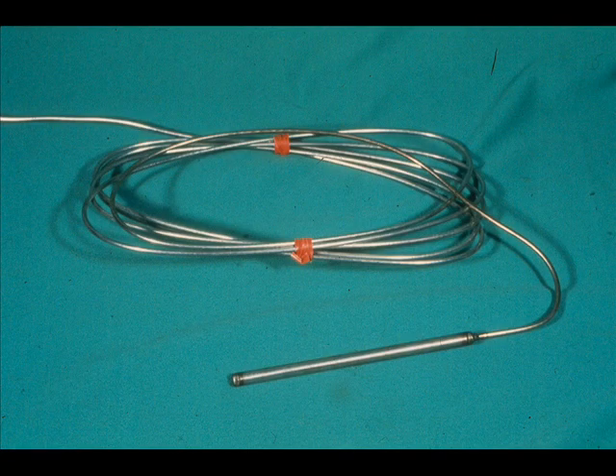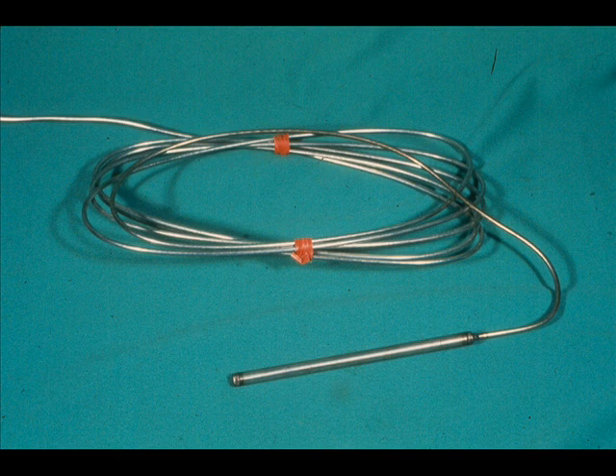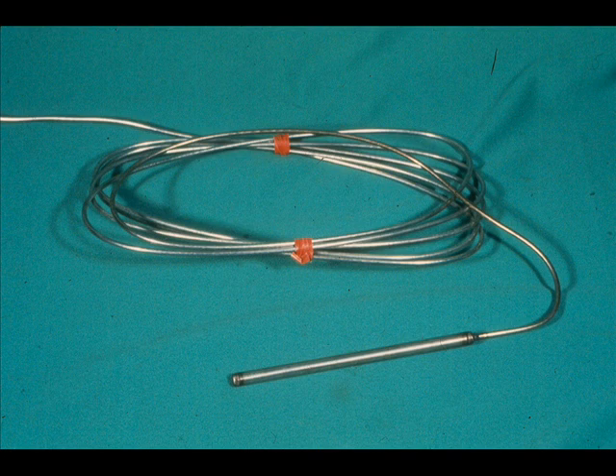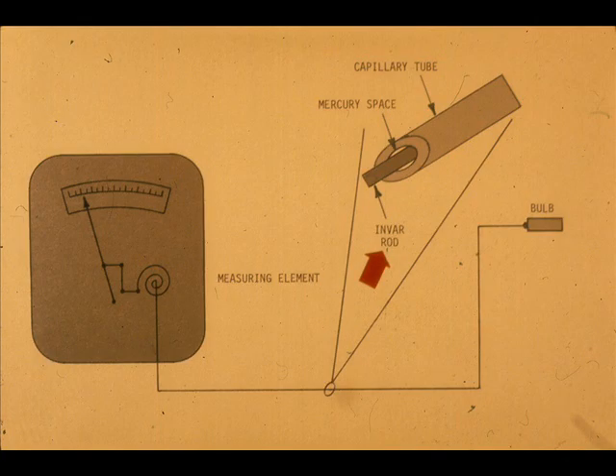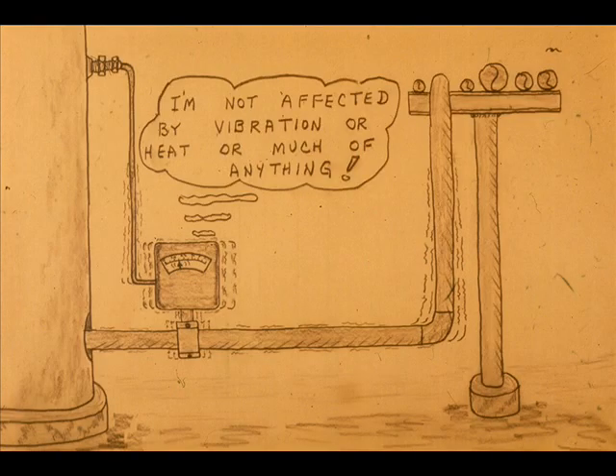The high filling pressure gives the mercury system a positive positioning action and good response speed. This high internal pressure also makes the system immune to changes in static head pressure caused by moving the bulb above or below the case. The case and capillary temperature compensation is accomplished the same way as in the liquid hydrocarbon systems. There is an exception. One manufacturer uses an invar rod inside the capillary tubing to compensate for ambient temperature changes.